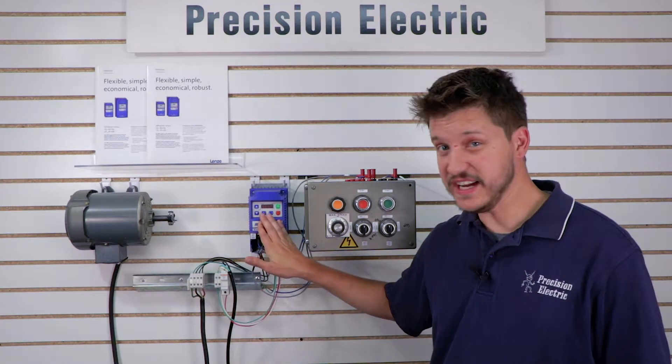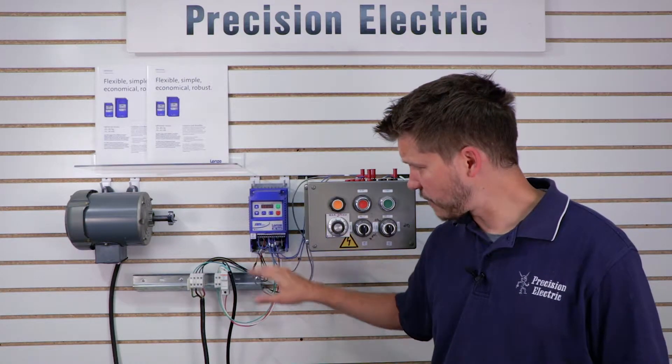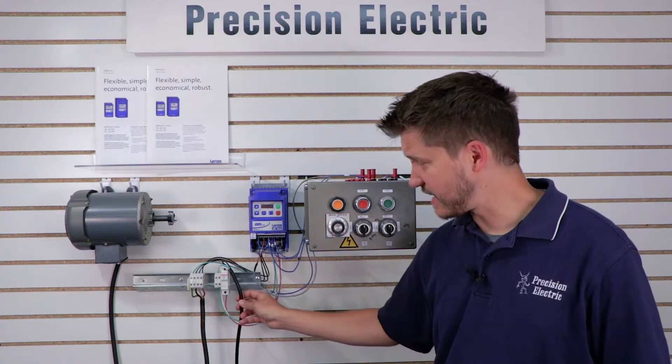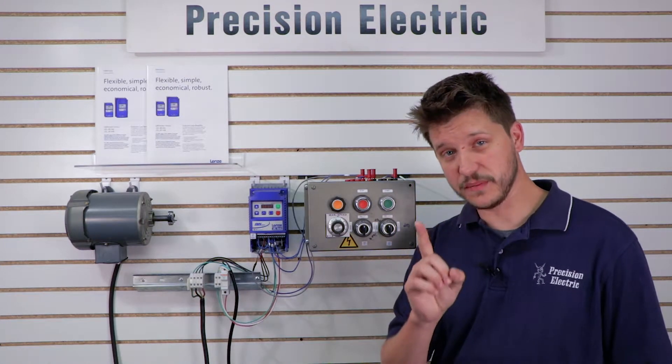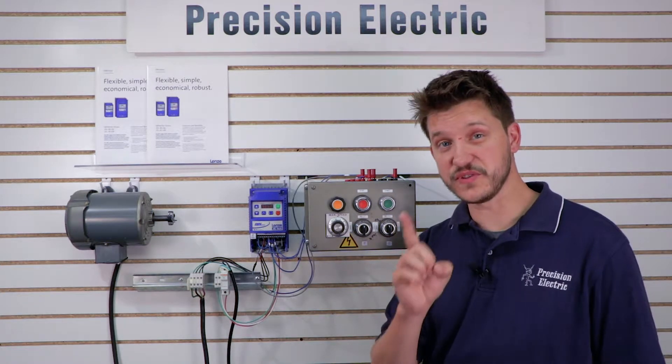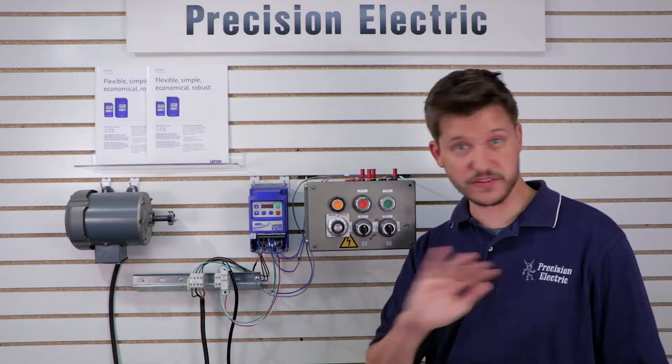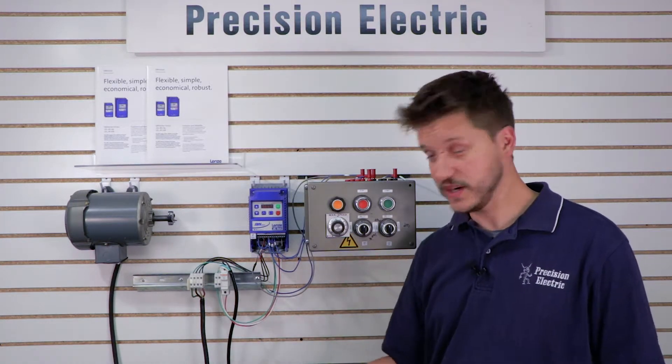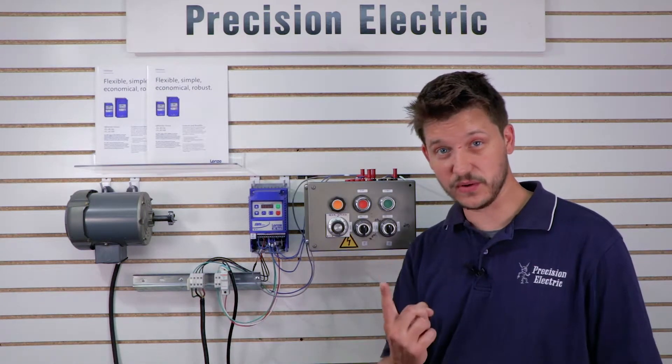So let's start with the drive. In order to protect the drive, any drive, we want to make sure we wire fuses to it. In my instance I've got a single phase drive, so I've only got one hot wire coming in. In general, when you're fusing a drive you need to make sure you fuse every single hot wire. If you have single phase 230 volt and it's got two hot wires, you have to fuse them both. If you have 120 volt like I do, I have a hot and a neutral, I only have to fuse the hot so I only need one fuse.